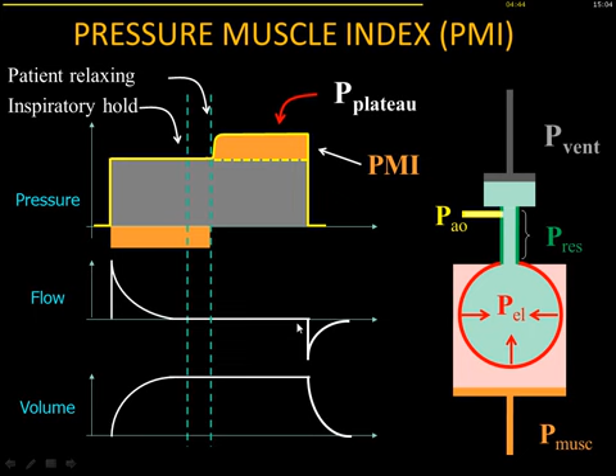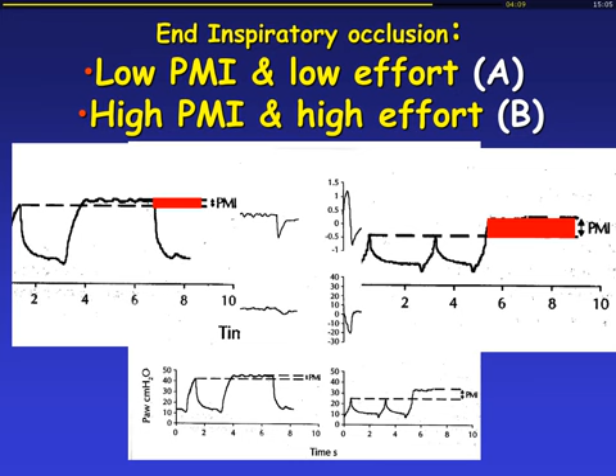Here you see a patient with a rather high level of pressure support compared with one with a lower level of pressure support, almost CPAP. And you see that the change in pressure at the end of this breath is very small, while it's much bigger during CPAP. Why? Because the contribution of the patient at end inspiration is much higher when the level of support is lower. And you don't need esophageal pressure to do that. You just need to push a button and read the pressure.